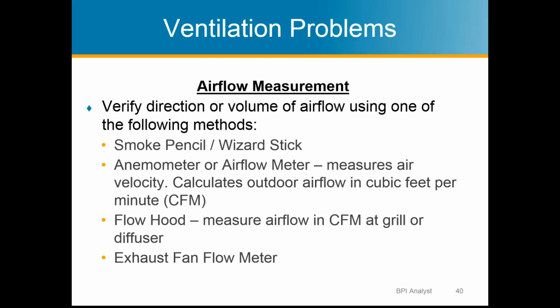A flow hood can be used, but usually in ventilation, most bathroom fans are rated at 50 CFM, and most of them operate somewhere between 25 and 30 due to the static pressure in the ductwork. So at that low of pressure, most flow hoods are not accurate. Flow hoods are typically for HVAC duct systems. The favorite method of measuring exhaust fan flow is using an exhaust fan flow meter. It's much more accurate and quite easy too.